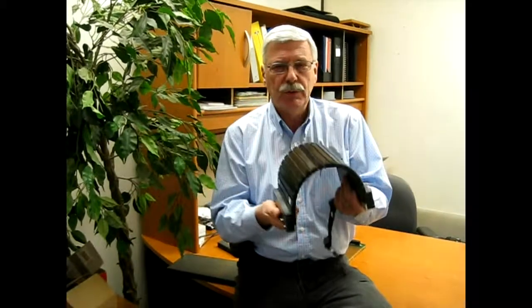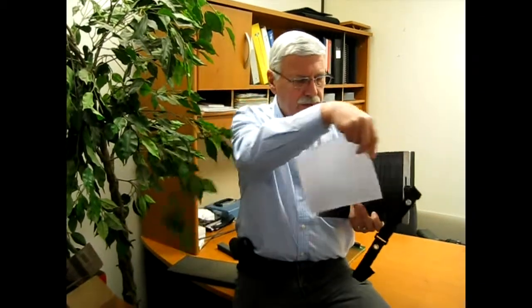I'm here to tell you about an invention we've made that will make it easier to detect corrosion in pipes, whether under insulation or internal corrosion inside the pipe. The invention is a flexible probe called a blanket probe. It can be placed on the pipe, flexes in two directions, and handles any size pipe. Inside are 256 sensors laid out in a pattern that detect electromagnetic energy affected by the pipe wall thickness. Regardless of whether the pipe is insulated or bare, we can detect internal or external corrosion.